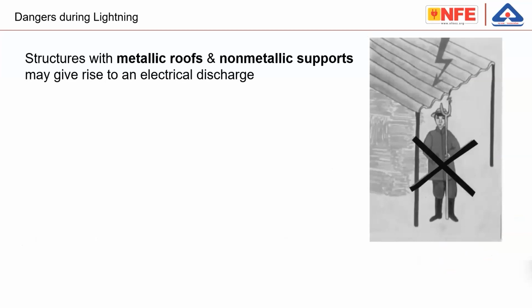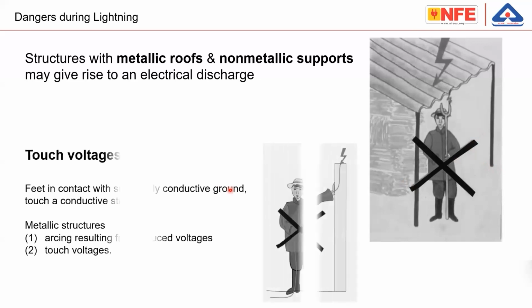The third dangerous part: don't stand under an unearthed metallic roof. You can find these wordings in the standard: structures with metallic roof and non-metallic supports. This means if the support is also a metal pipe, you are safe. But if the supports are non-metallic, the situation is dangerous—the lightning may hit the sheet, and from the metal sheet the discharge may happen to the person. So this is dangerous.